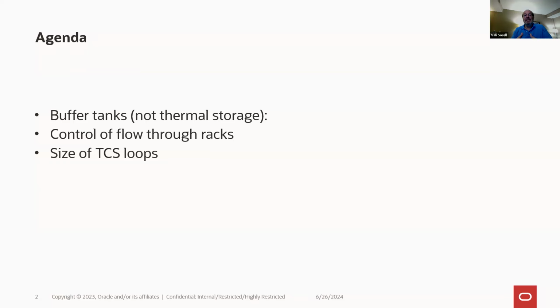And so the three issues that I see and have had to deal with as we're going into multiple data centers are what to do about very quickly or rapidly changing loads. If a cluster of servers increases their capacity from literally idle condition to 100% in a few milliseconds, how does the mechanical system respond to that? So in my way of viewing it, probably putting buffer tanks in the system is the best approach. Also, how do you control the flow into the racks, the IT racks that are liquid cooled? I thought it should be trivial. It's actually not that trivial, but it's a very interesting thing.